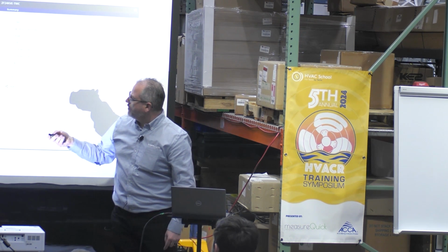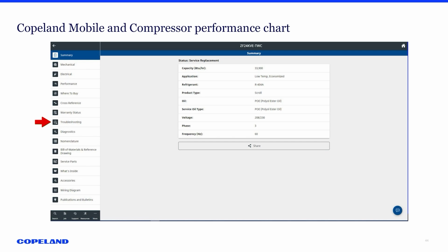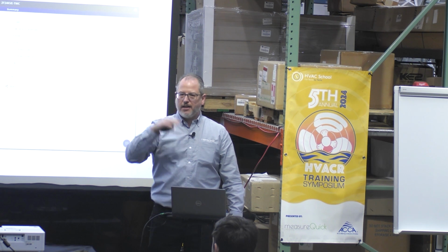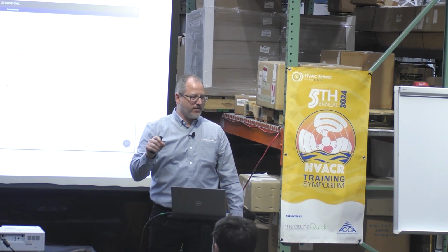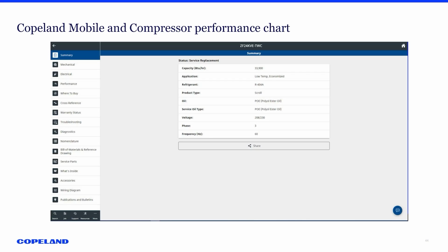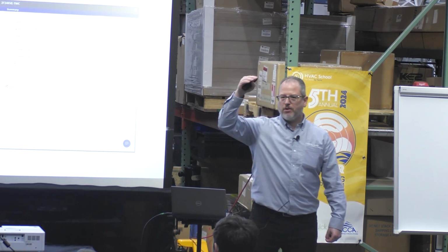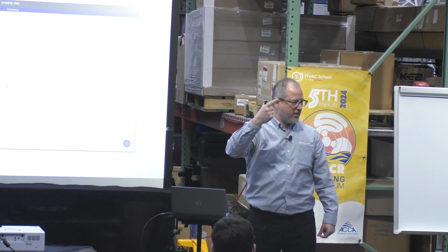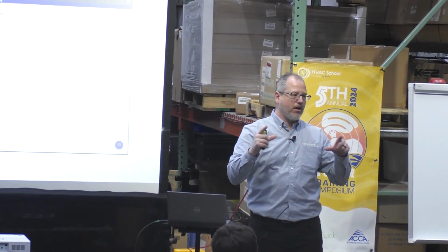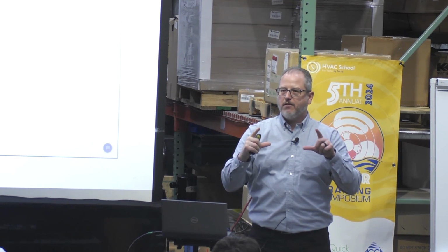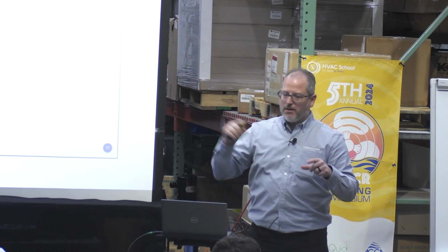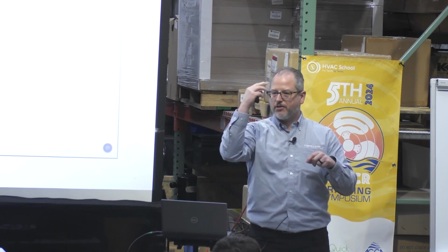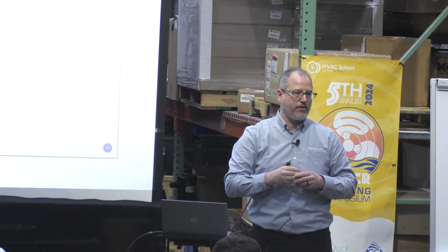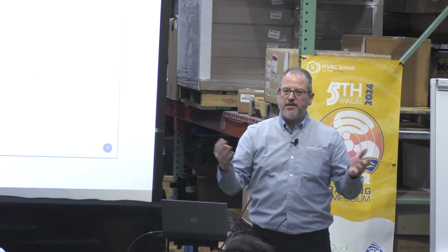But if you just want troubleshooting information, there are just questions. When you go to the troubleshooting one, you just start answering questions. And then at the end, it'll tell you, do not replace the compressor if you don't have to replace the compressor, right? The diagnostics is a really cool thing. If anybody has not used that, you actually put your pressures, your amp draw, and your voltage in there, and it will tell you how far off you are with those parameters from what it should be. And then there'll be a button that says troubleshoot, and you push that button and it'll tell you exactly the steps to go through to look for things, okay? So we try to make it as easy as possible for everybody out there.